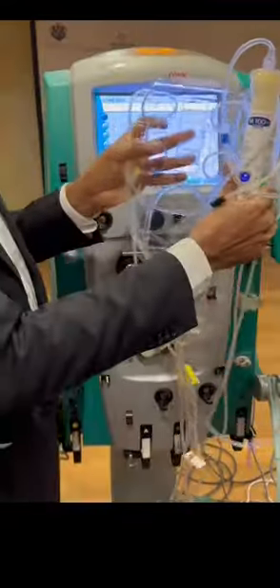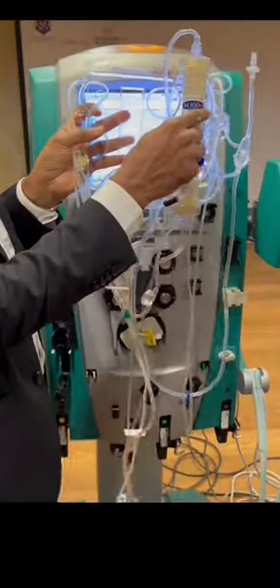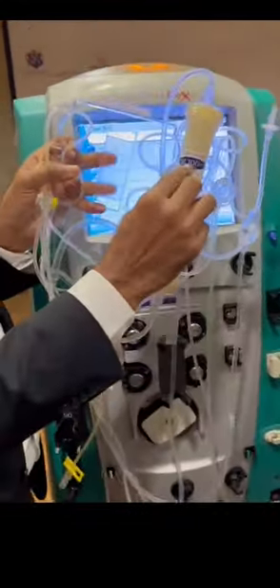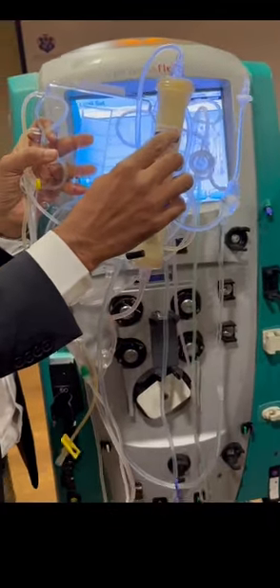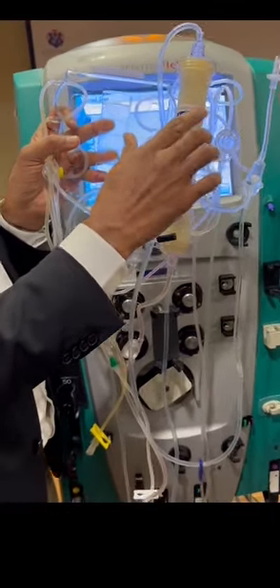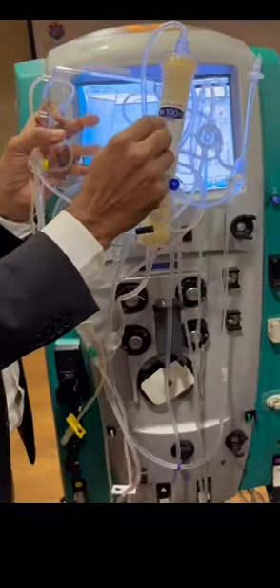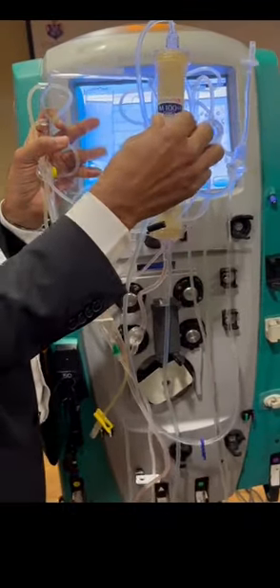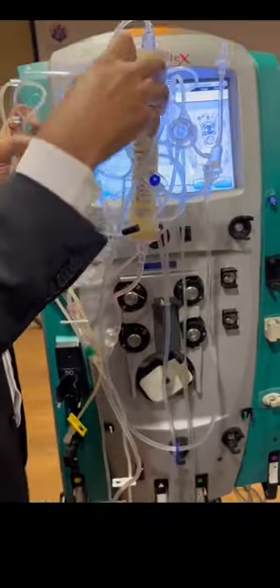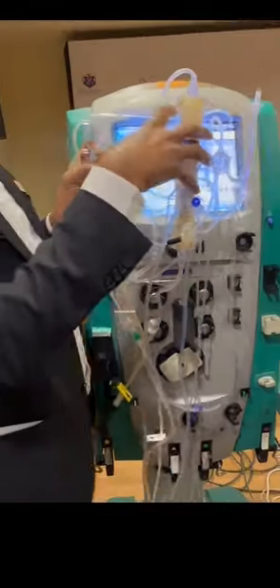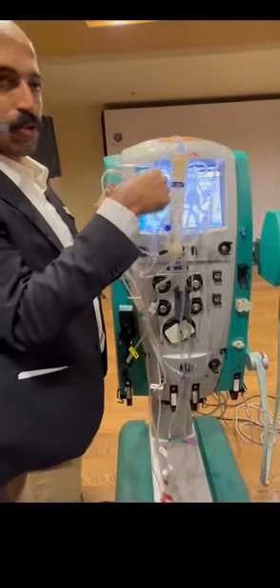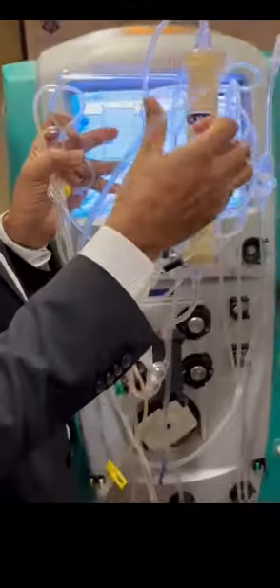Okay, so I will show you how to connect the filter. This filter is a Prismaflex M100. We have multiple types of filters: M100, M60, HF20 and Oxiris. These are the four filters available in India for CRRT. The M100 is the adult filter. The surface area is 0.9, and the blood volume, including the dialyzer and the tubing, is 152 ml.